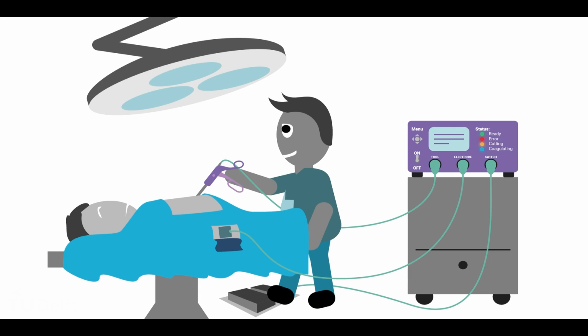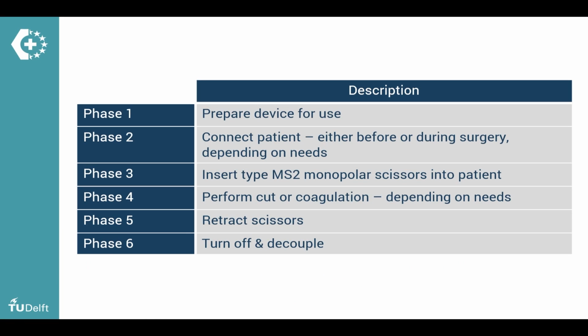For our electrosurgical system, we'll go through each of the phases of the intended use process that you just read about, and then for each of these phases, we will take some steps for which we'll try to come up with a hazardous situation and a consequential harm while considering the 6 aspects of the intended use. When useful, we'll indicate whether these are random faults or systemic faults.